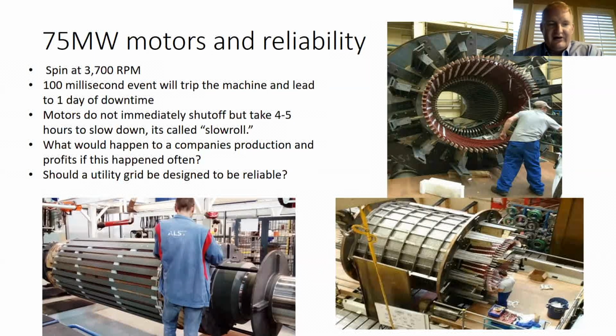Again, within 100 milliseconds it will shut the motors down to protect the integrity of the machine so it doesn't destroy itself. But the problem is they go into what they call a slow roll. You have your rotor that fits inside your stator, and as it slows from 37 to 36 to 34, that takes about 4 to 5 hours. Total stoppage is about 6 hours, and then it takes another 6 hours to get back up and running for production.